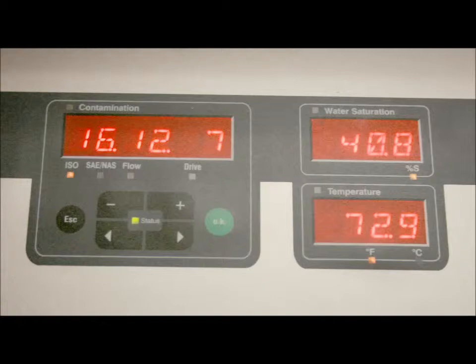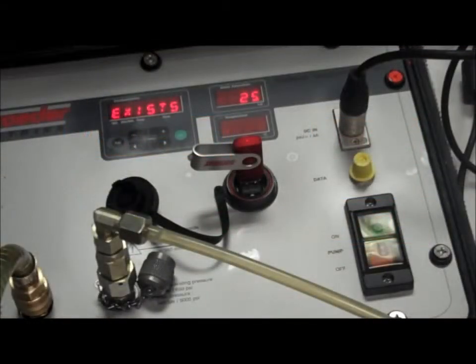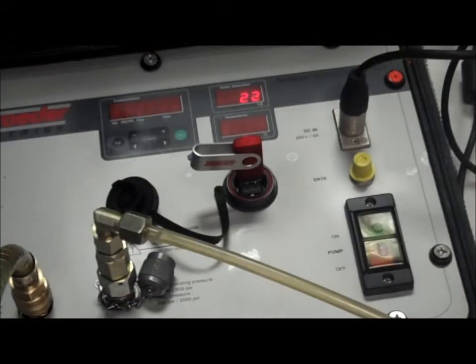If you want to download the information that you've now obtained, there's the USB port, and you can see here we've attached the flash drive to the unit. This unit stores 20,000 data points, and you can download all 20,000 data points if you've been running this as an in-line sampling unit. But in this case, we're running a bottle sample, so it'll download that particular information.